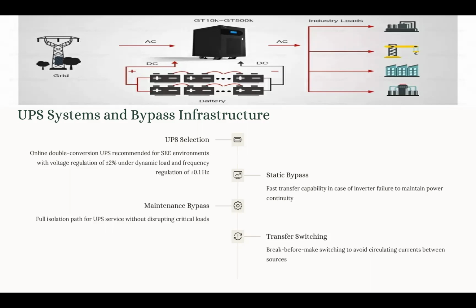Now, we also have maintenance bypass, which is a manual bypass, and it is normally used during UPS services. We also have a transfer switching method, which is break before make. This is recommended by IEEE 1100, and it prevents parallel source connection, so it avoids circulating currents. This is important because of the make before break transfer switching method. Make before break is not recommended for sensitive electronic devices, as temporary source overlap can introduce transients or overloads, and this is the reason that make before break transfer switching methods are not recommended for sensitive devices.